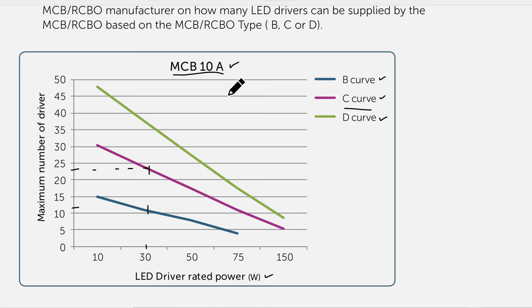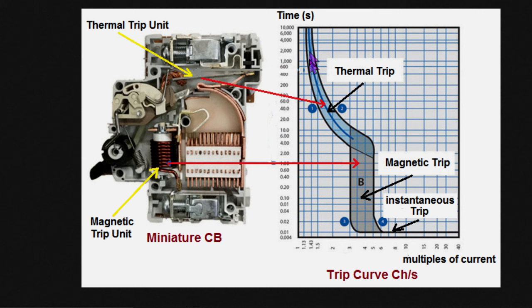Getting back to the diagram, remember it's just a general recommendation — it depends on the circuit breaker used and the manufacturer. Some circuit breakers even state how much instantaneous current they can withstand before tripping. Inside a circuit breaker there is a thermal trip section: it heats up as current flows through it, offering a slower response. If you've got a 10-amp circuit breaker pulling 12 amps, it's probably not going to immediately trip — it will have to heat up first, which according to the curve could take a couple of minutes.